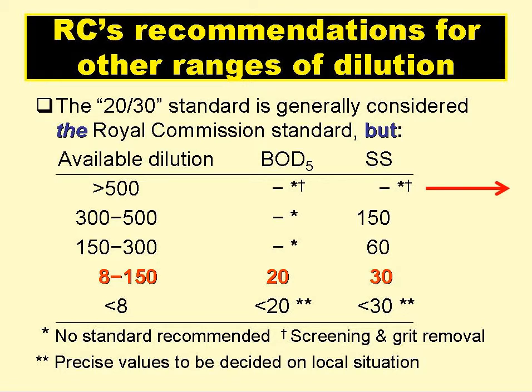Actually, the 20:30 standard wasn't the only one recommended by the Royal Commission. The commissioners recommended a range of standards depending on the dilution available. They applied their 20:30 standard to dilutions in the range 8 to 150. For dilutions less than 8, the precise values for BOD and suspended solids were to be set based on the local situation. For dilutions greater than 150, they recommended only standards for suspended solids. And when the dilution was greater than 500, no standards were deemed necessary, and the wastewater only required screening and grit removal.